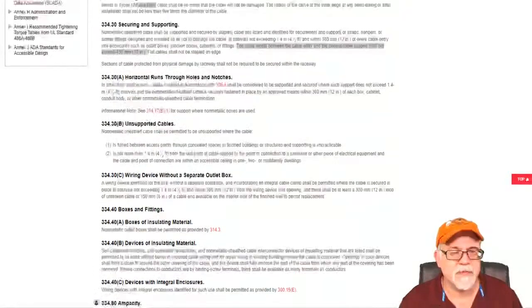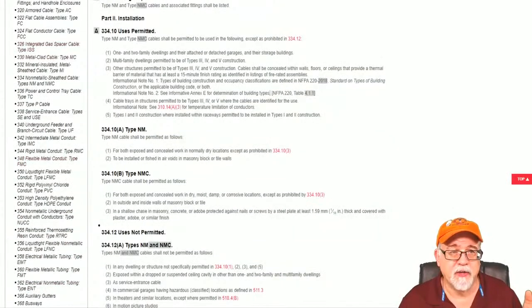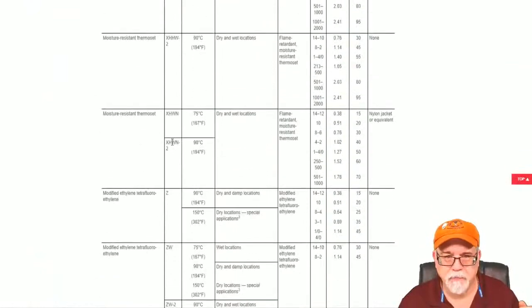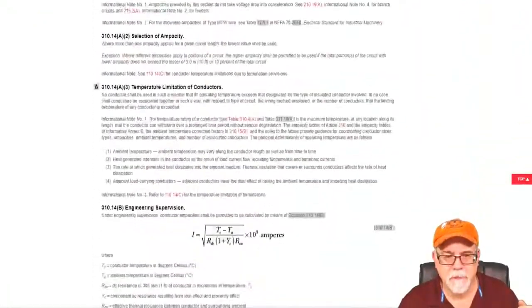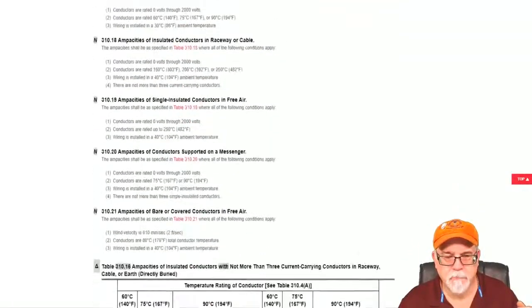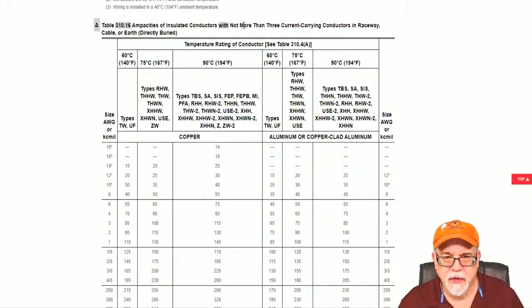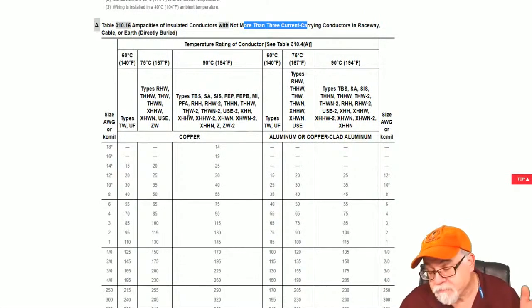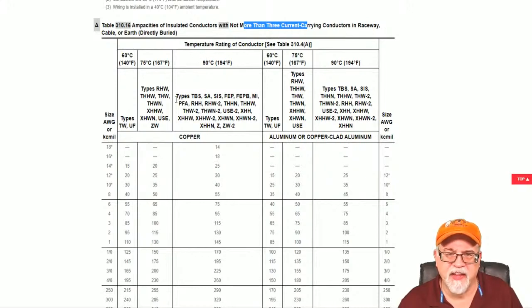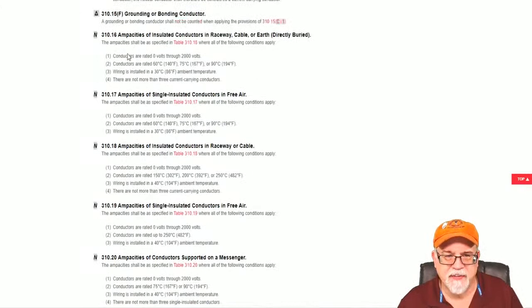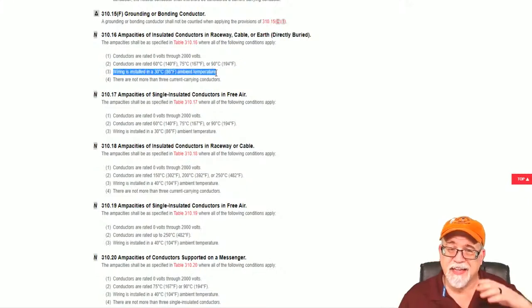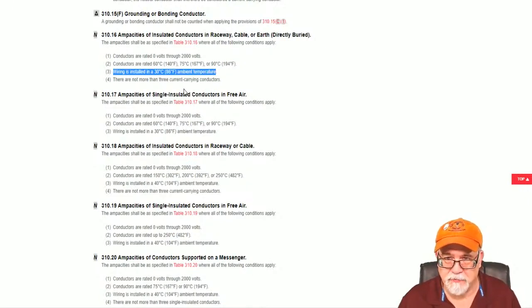So now, what I want to do is go to 310.16, or if you're in the 2017 code, guys, 310.15(B)(16). Okay, so here we are. Here's the ampacity. It's not more than 3 current-carrying conductors, and there isn't. It was an 8-3 with a ground, so it's not going to be more than 3 current-carrying conductors. Of course, the ambient temperature, you wonder, where is that in here anymore? You notice that's missing? That's because 310.16 has its own actual section now, you see? And this is where it says wiring installed in 30 degrees C, 86 degrees Fahrenheit. And of course, in our case, it is not 86 degrees Fahrenheit. It's 140 degrees attic or 130 degree attic or whatever it was. We'll go back to the question.